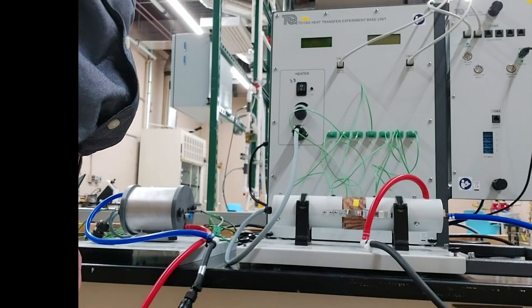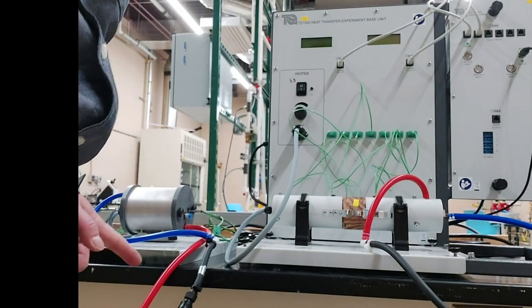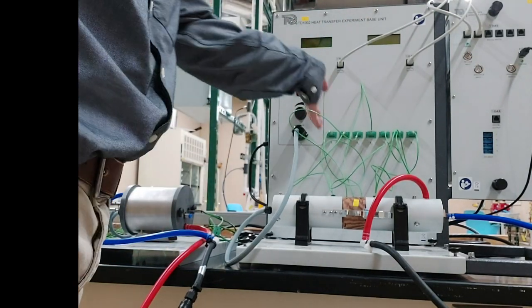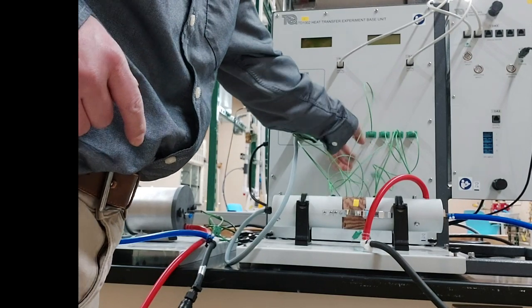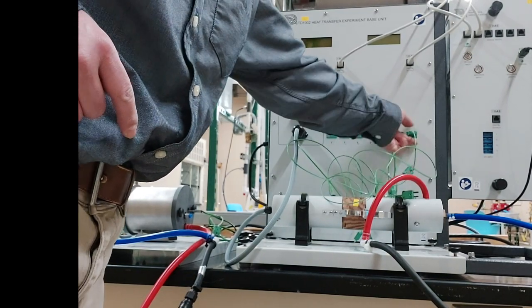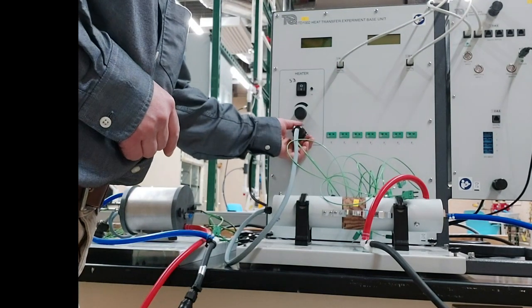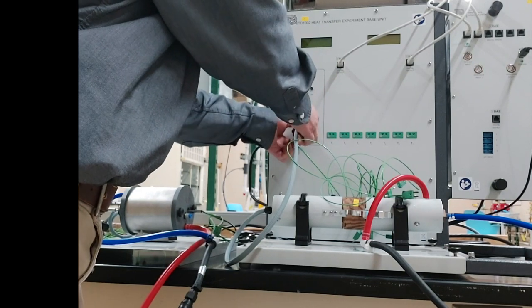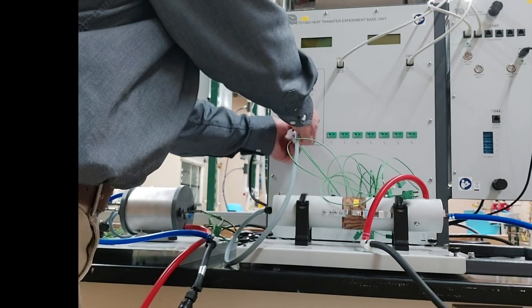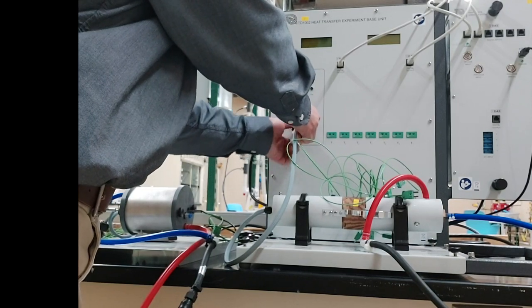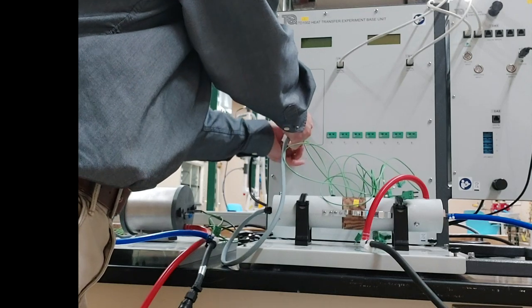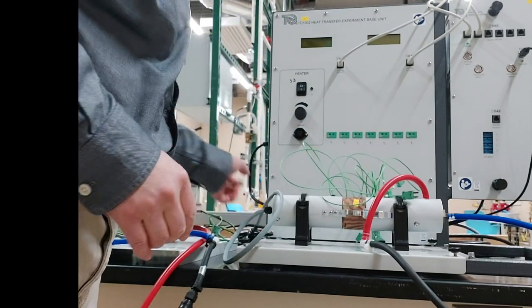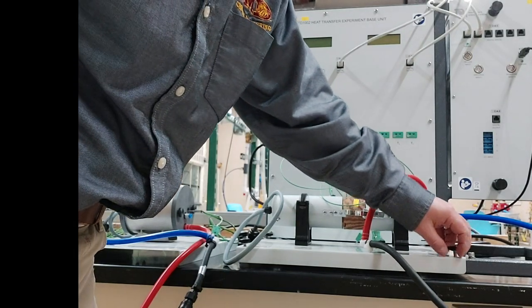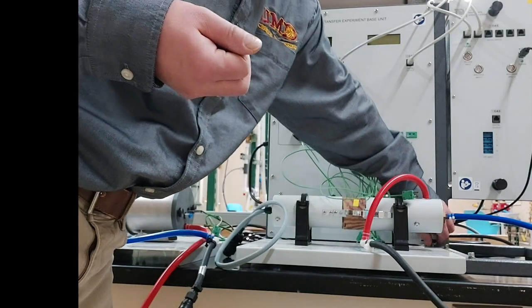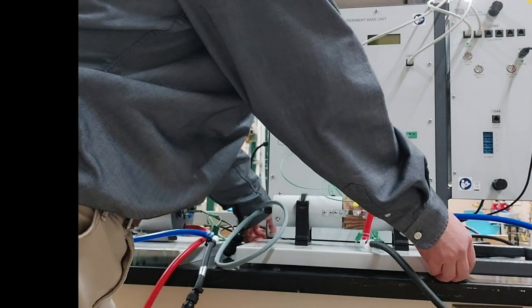To swap the two instrument modules, first you need to make sure everything is off. Next, you will disconnect all thermocouple cables from the control panel. Then disconnect the heater power cable by holding the plug piece close to you and turning the other plug piece close to the panel counterclockwise. You can pull it out when the plug becomes loose. Then remove the 4 screws that fix the module's white base to the instrument's gray metal frame. Now you can lift the entire module like this and move it to a side on the bench.